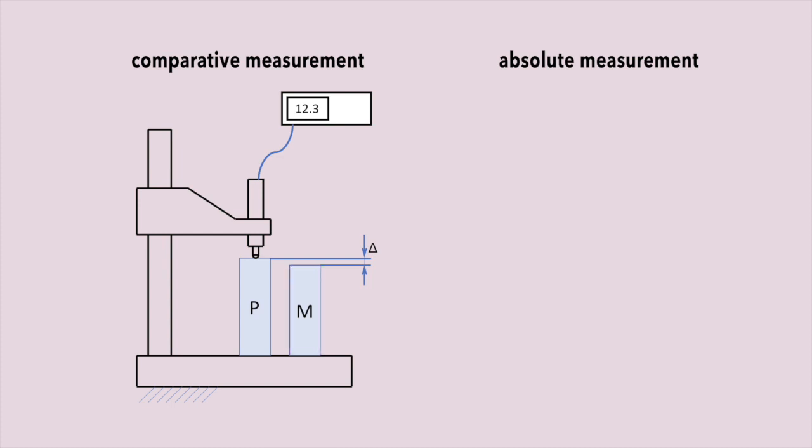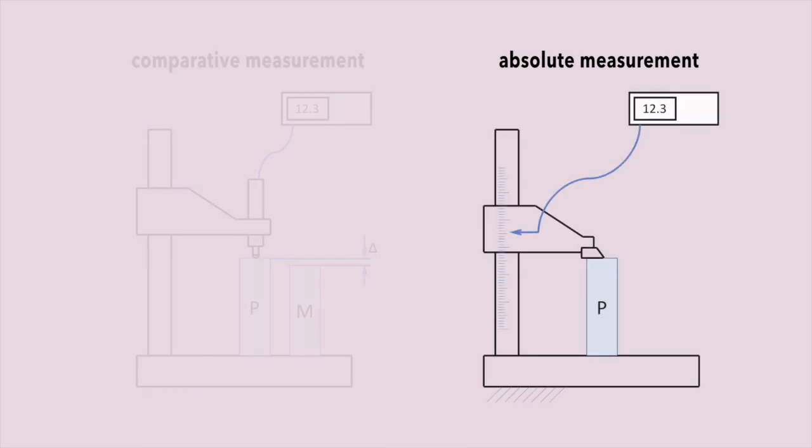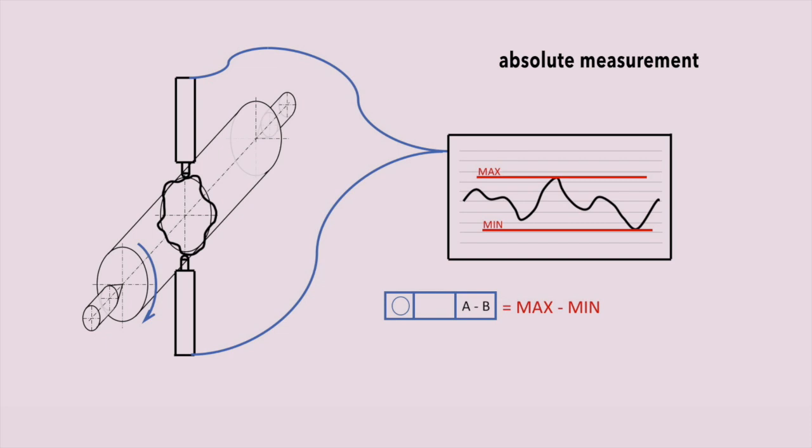In absolute measurements, the master is not needed. This is typically in cases where the scale has a fixed reference, like measuring the length with the scale starting from the base at zero, or where the measured dimension is itself relative, like a difference of the extremes in roundness.